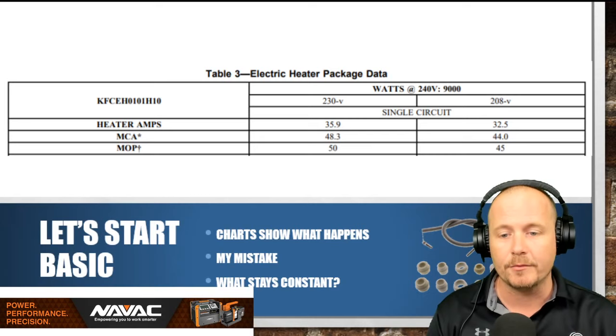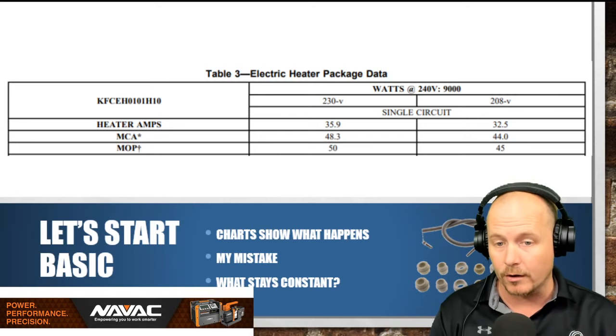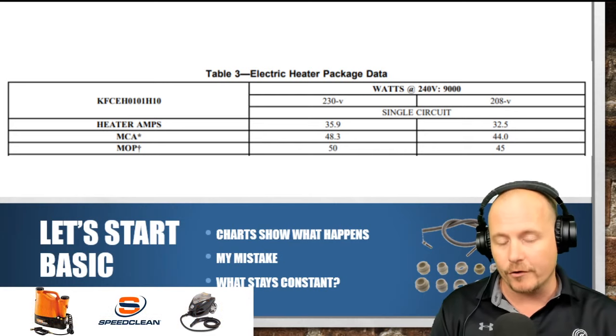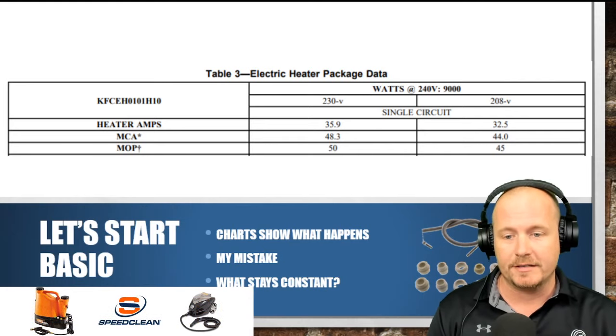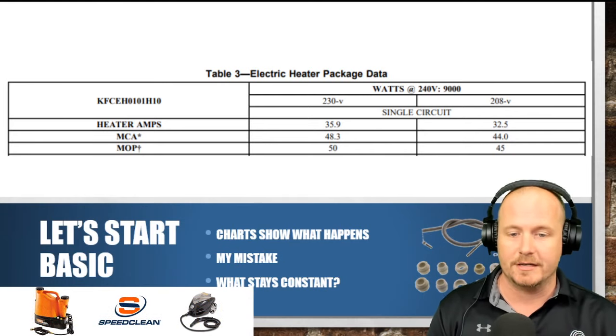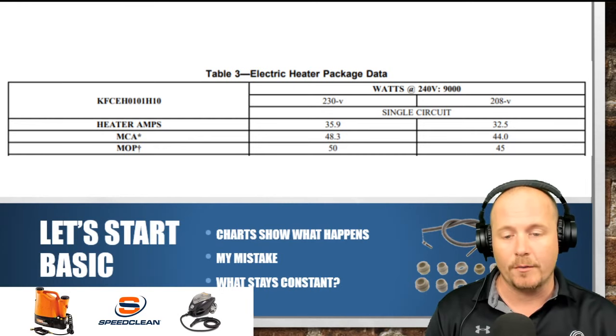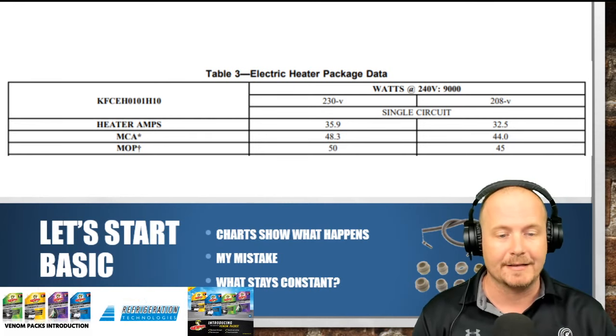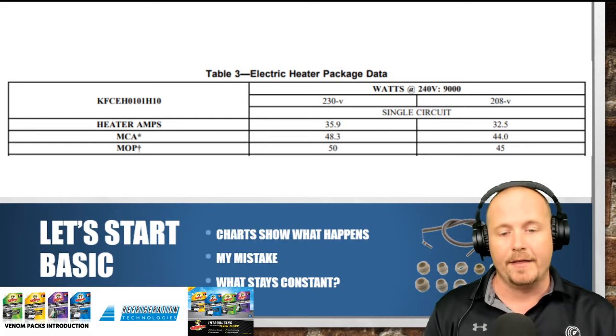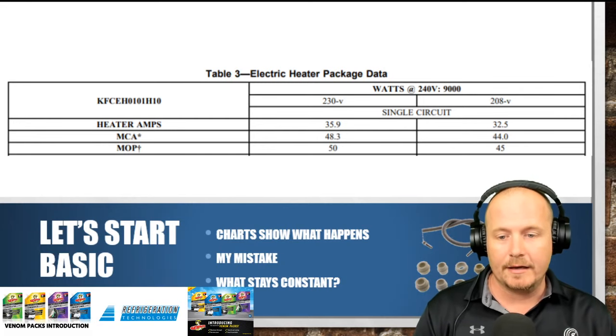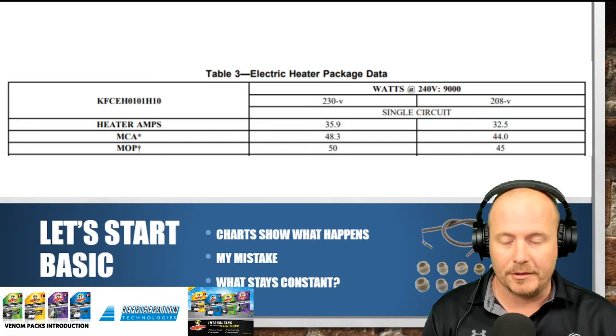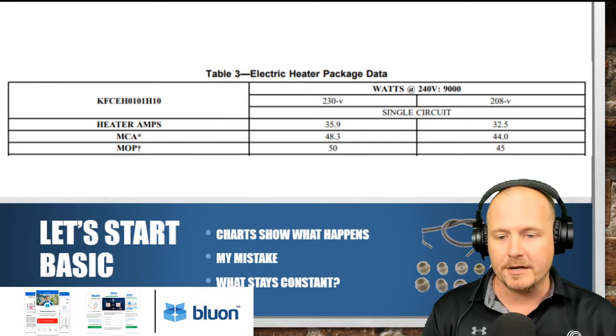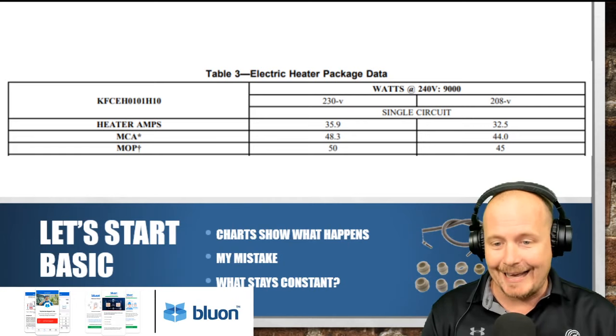Then at 208, when you decrease the voltage even lower, the amperage further decreases. To see the wattage of this heat strip at 208, you take 208 and multiply that times 32.5, and that will tell you the wattage. The point is that when you decrease the voltage, you decrease both the amps and the watts.